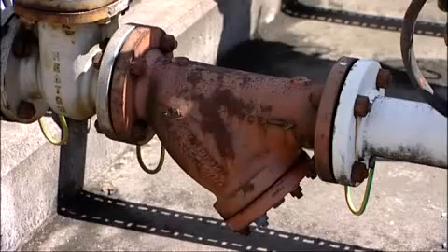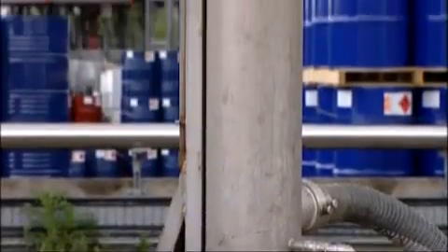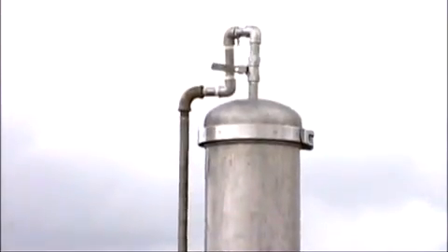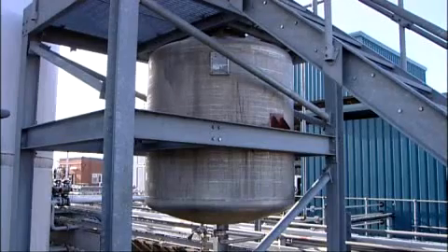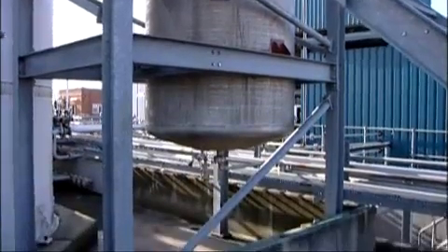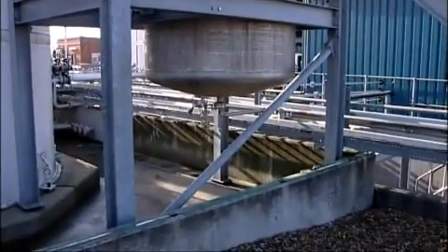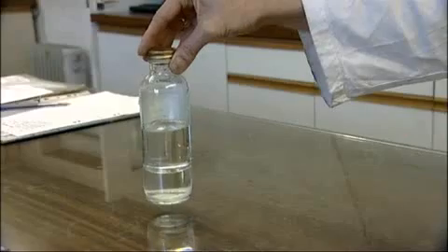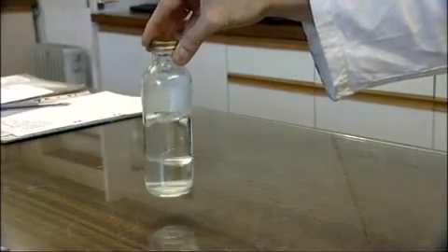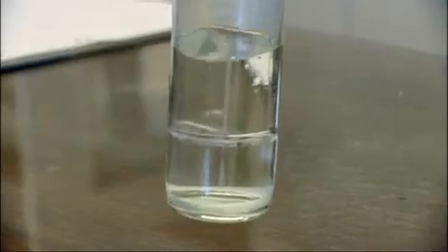Filters, because of their large surface area, can generate as much as 5,000 times the electrostatic charge generated in a pipe system without filtration. Dispersing operations can be particularly hazardous in view of the extremely high rate of charge generation when particulates are present. High charge rates can also occur when liquids containing non-miscible components are mixed or agitated. With poor conductive liquids, the charge accumulation can cause sparking in the vapor space to an exposed agitator blade in a mixer or to a filling pipe.